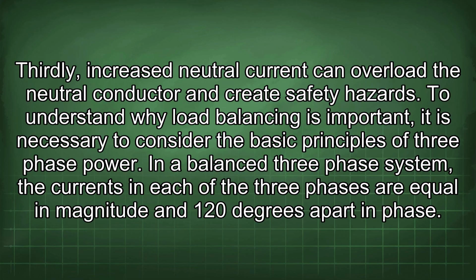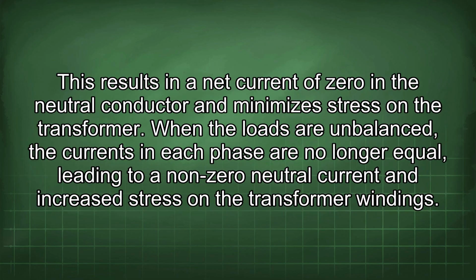To understand why load balancing is important, it is necessary to consider the basic principles of 3-phase power. In a balanced 3-phase system, the currents in each of the 3 phases are equal in magnitude and 120 degrees apart in phase. This results in a net current of 0 in the neutral conductor and minimizes stress on the transformer. When the loads are unbalanced, the currents in each phase are no longer equal, leading to a non-zero neutral current and increased stress on the transformer windings.